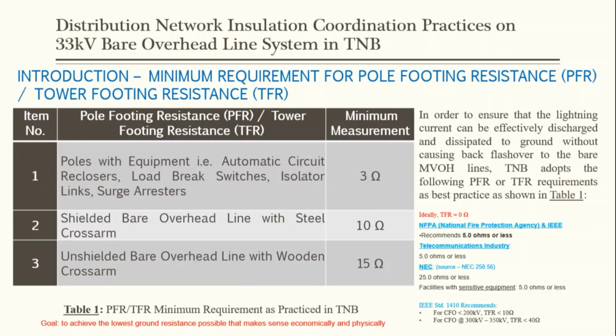All right. Ideally, of course, we want the TFR to be 0 ohms, but that would be impractical and maybe not economically viable. Okay, so our goal for having this minimum requirement for PFR and TFR will be to achieve the lowest ground resistance possible that makes sense economically and physically, right? So we have a few references. For example, the National Fire Protection Association and IEEE recommending 5 ohms or less for the telecommunications industry, 5 ohms or less for the earthing measurement.